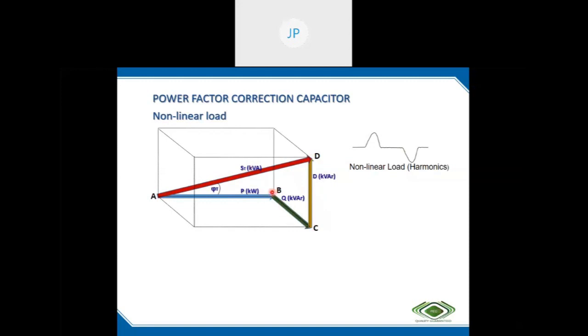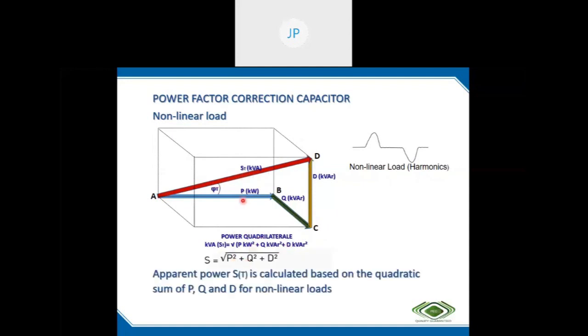So this is decided by two factors: one is reactive power, the other is THD. The sum of all these squares, the quadratic sum, is the true apparent power ST. It is calculated as the quadratic sum of P squared, Q squared and D squared. Here the power factor is P by ST, not P by S. The net true power factor will be based on these two influences.